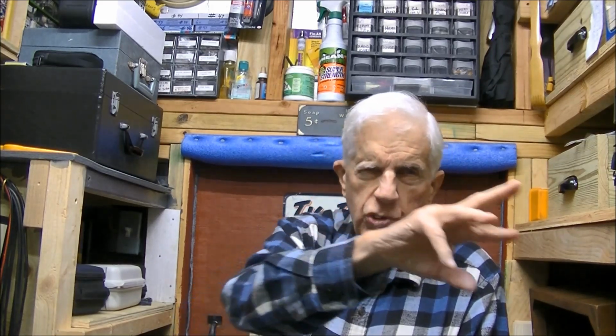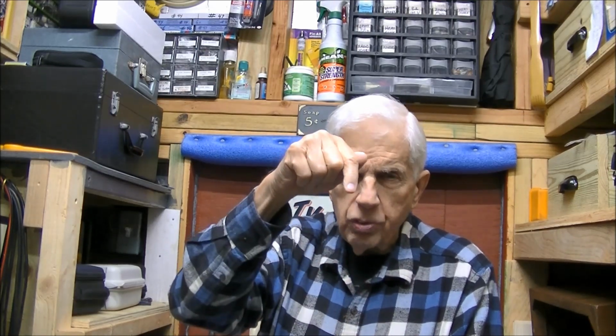However, the ground wire from the 3-prong plug that goes into the wall comes out with the green wire connected to an eyelet and bonded to the chassis of the isolation transformer. The output jacks, of which there are 4 but I'm only showing 1 since they're all in parallel, still have their ground prong connected to the case. However, the neutral is floating along with the hot, I should say.